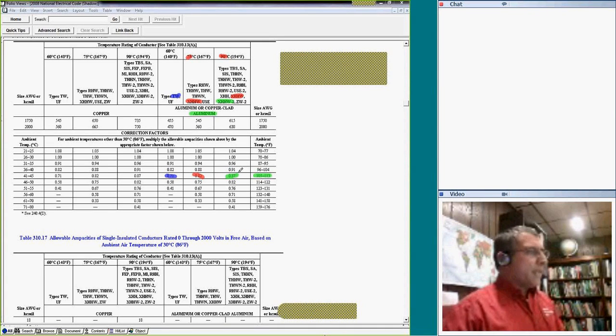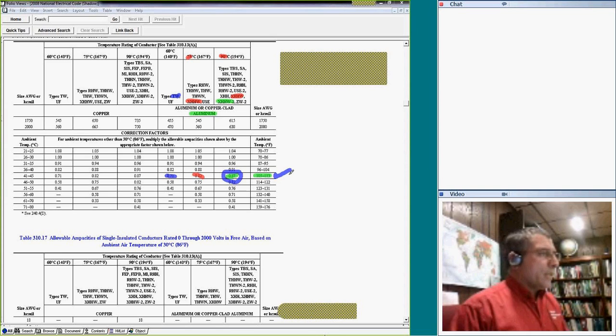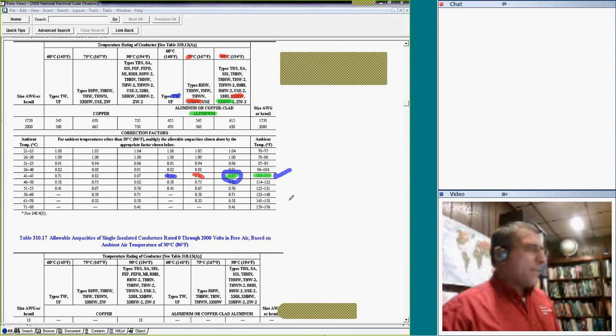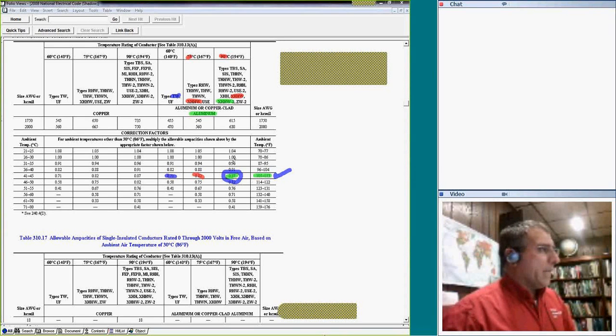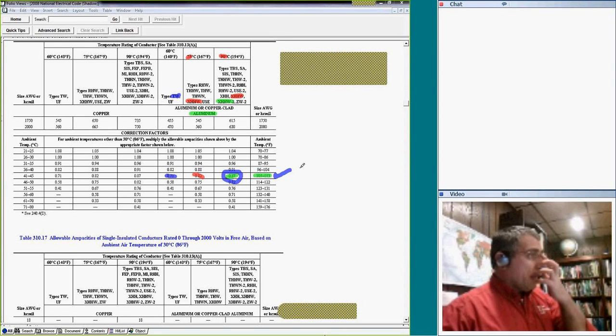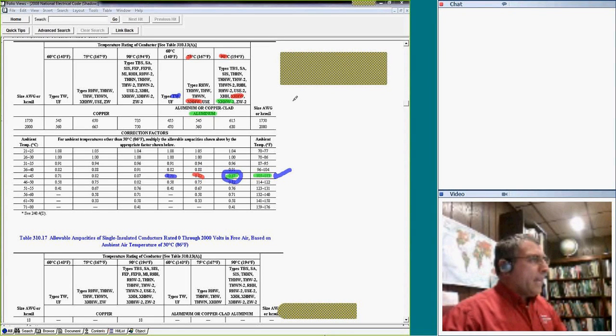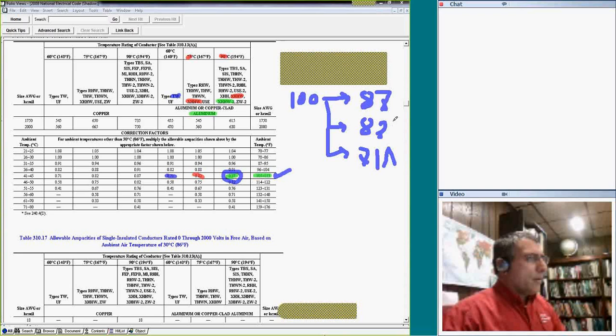Now, which one do you think is more economical to use if I have a very high temperature like this? Of course, to use an XHHW-2. That was the best application because you can get more amps. Just to give you an idea, if the conductor was carrying 100 amps, based on the first you get 87 amps out of it. Based on the second, you get 82 amps out of it. And on the third, you get 71 amps. Now you get fewer amps from the conductor.